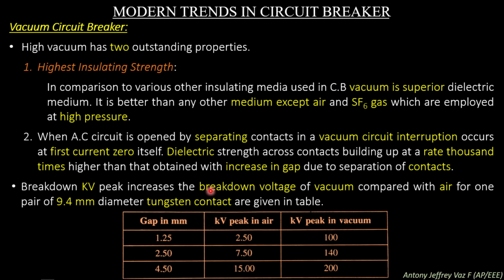The breakdown voltage of vacuum compared with air for one pair of 9.4 millimeter diameter tungsten contacts is given in a table. On comparing here, the gap in millimeters for the contacts opening is shown, and the kilovolt peak in air and kilovolt peak in vacuum are shown. Here you can see 1.25 millimeter contact separation is needed to break 2.5 kilovolt peak in air, whereas with the same 1.25 millimeter contact separation we can break 100 kilovolt in vacuum.